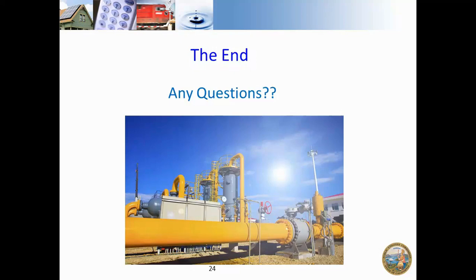The grandfather clause is mainly applied to the cathodic protection (CP) system. Parks that were installed before 1970 are not required to have a CP system installed. But if they upgrade their system, they are then required to install a CP program. If they don't do any operating, repair, or upgrades, it's okay — they don't have to comply with the CP requirement.